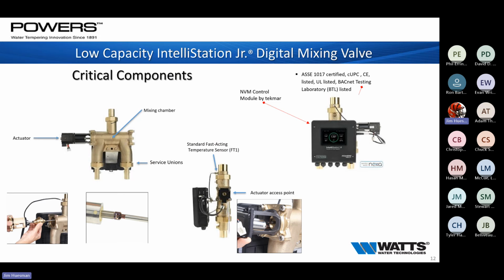So they really made it so you're able to dive into every feature of this valve and really work on it. Come up here to our top left, you'll see we've got our hot and cold water entering through the bottom. We add service unions to both sides because, again, if you need to work on this, we don't want people cutting things out. Just a simple union, and then we're disconnecting it, and we can actually have the valve out of the system, either to change it or to work on it.